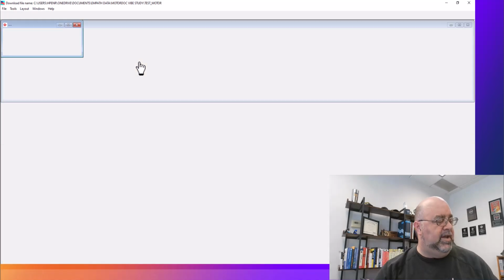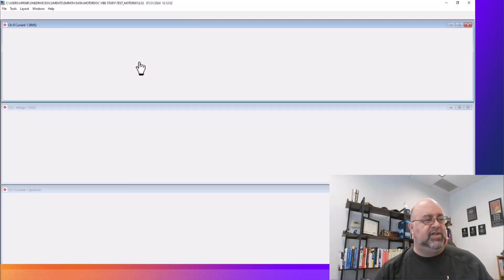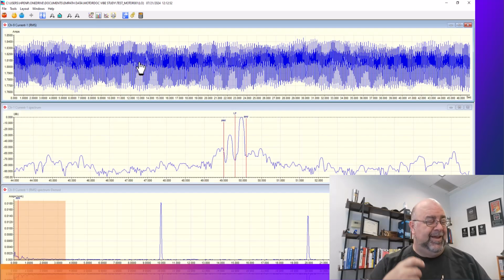Also did discover, by the way, with the HikMicro, the acoustic imaging system, you have to make sure it's shut off. There's two settings for shutting off. One is a sleep mode that I wasn't aware of because it's not in the manual. And when you put it in sleep mode, it continues collecting. It continues what it was doing.